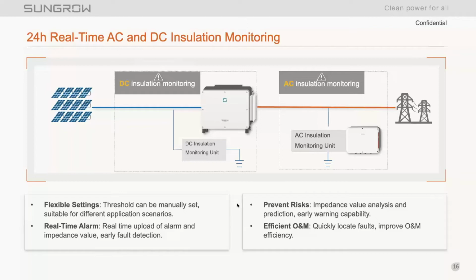And the other really cool thing about the advanced insulation monitoring that we're offering, both on the DC side and the AC side, is that we have kind of a predictive loop that's incorporated into the inverter software. So it's going to remember the values that it measures each day, and compare that to a certain time period before, and start to predict breakdown of equipment, and give you some intelligent recommendations for operations and maintenance.